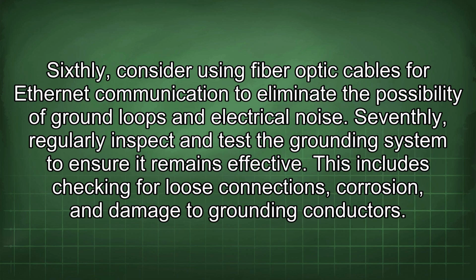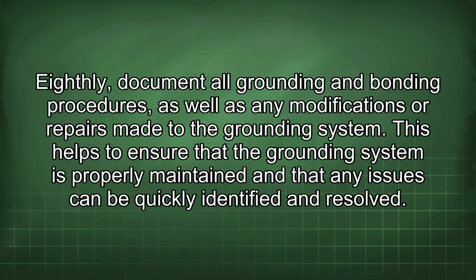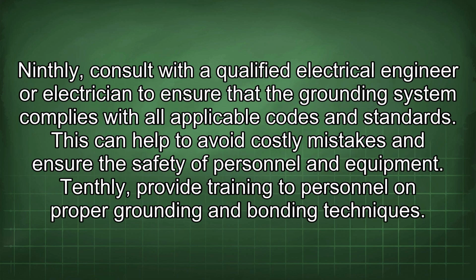Seventhly, regularly inspect and test the grounding system to ensure it remains effective. This includes checking for loose connections, corrosion, and damage to grounding conductors. Eighthly, document all grounding and bonding procedures, as well as any modifications or repairs made to the grounding system. This helps to ensure that the grounding system is properly maintained and that any issues can be quickly identified and resolved.